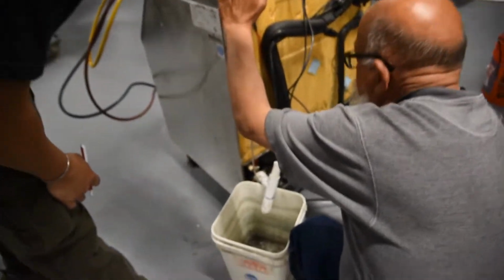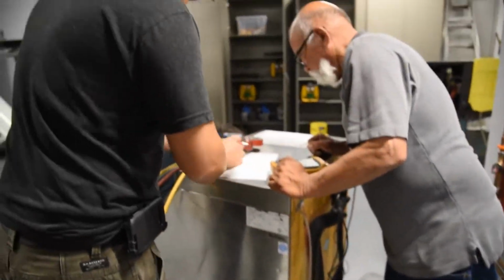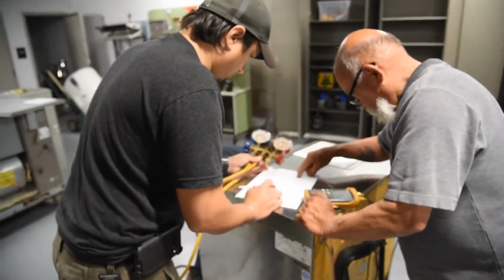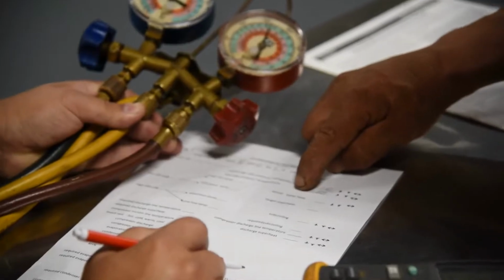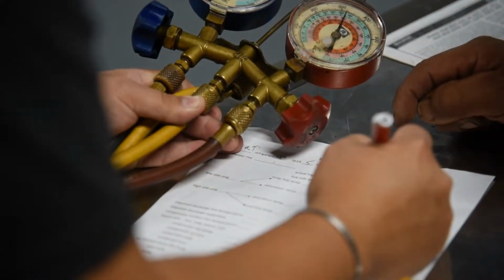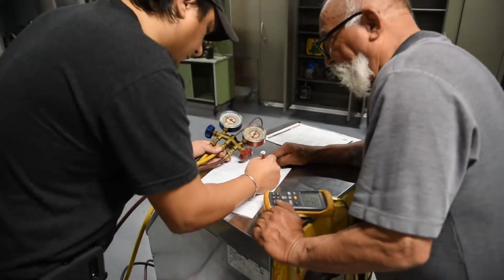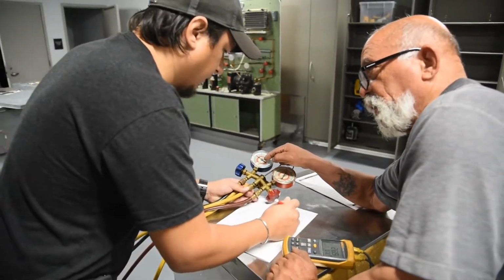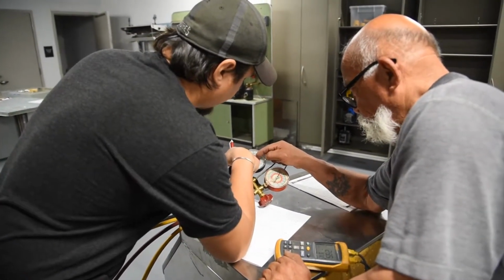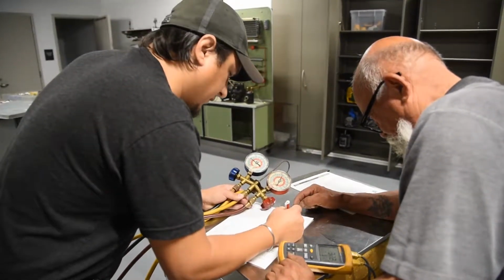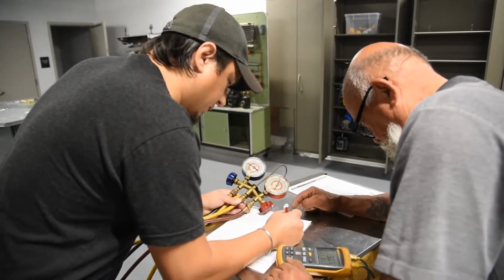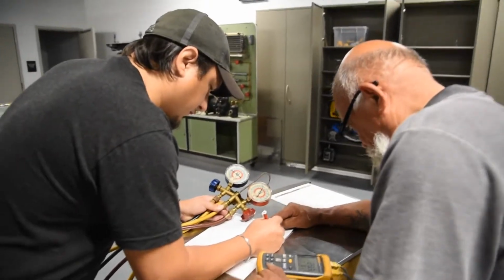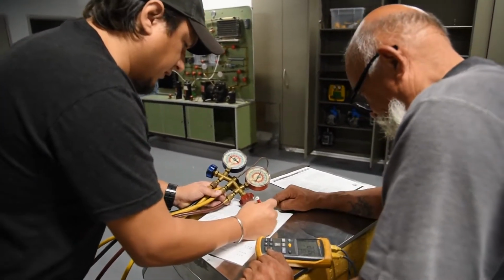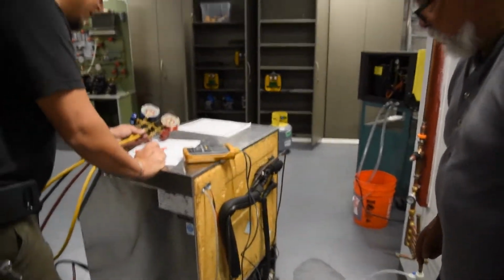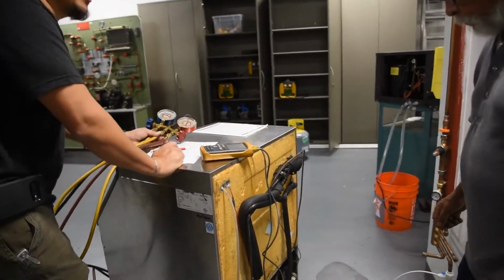Right here's the suction line. And go into the suction line and see what the temperature is on that. Suction. Good. Before harvest. Second before harvest. Okay, go ahead and put that in there. We had it on the low side, and the pressure was 0, and then the temperature was -10. Did you remember what the high side was? It was this actually. Okay. So 275, 110, and then on the low side it was 0 and -10 in temperature.